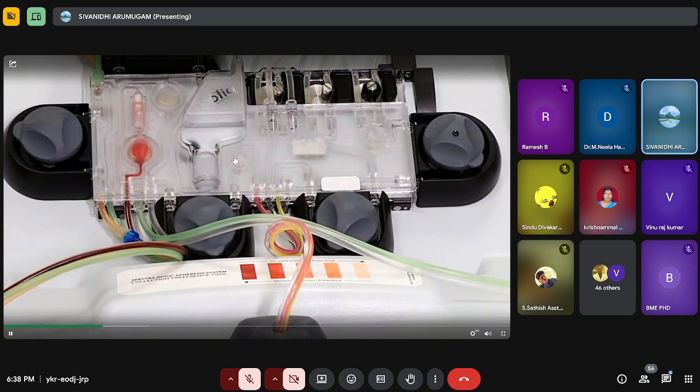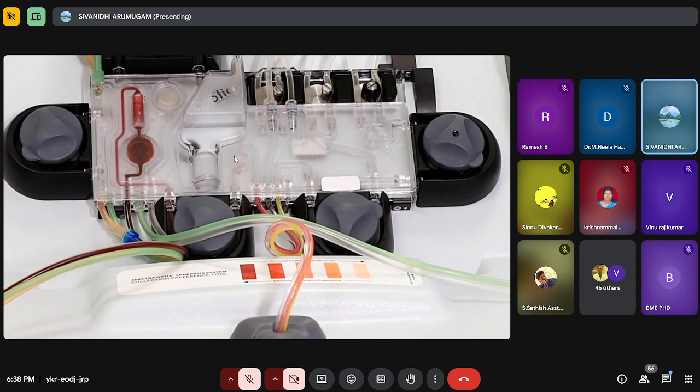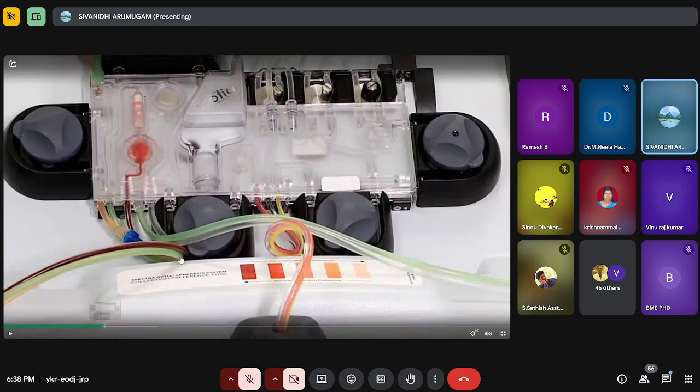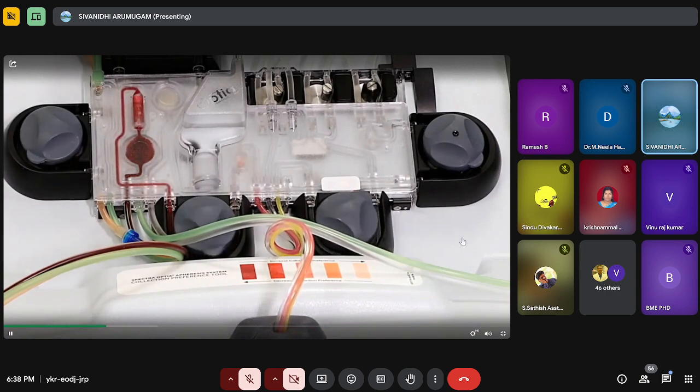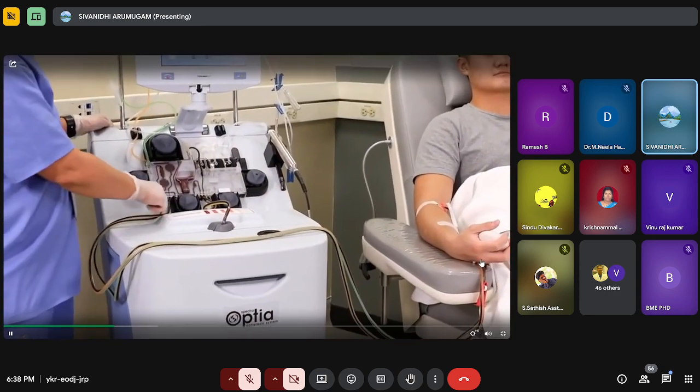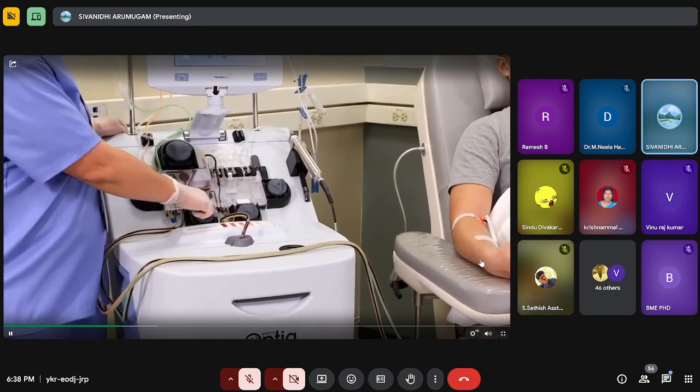Into the collection bag. See, now you've seen this flow, no? So it is going. This tube is called the centrifuge tube. Now this is going inside the centrifuge. You can see the path. The number of times the chamber is filled throughout the run depends on the patient's mononuclear cell count, goals of the procedure, and events that occur during the procedure.